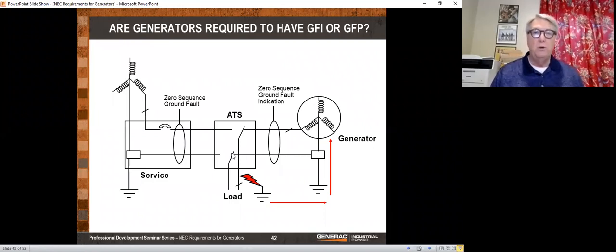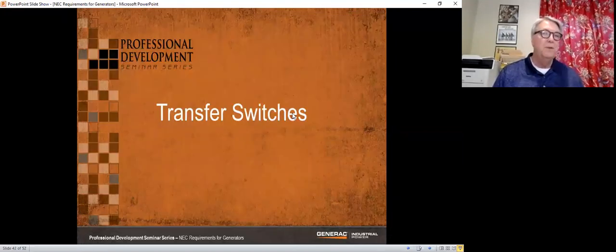If you used a 3-pole switch there, then this would just be a neutral bus bar. You wouldn't be switching that neutral. So now it would come out, it would go through here, then it would come down into your fault. But because with a 3-pole switch there would be no neutral to ground bond at the generator, it would have to come back through the service. And when it came back through the service, it would go through this zero sequence ground fault. It would trip your utility breaker. Then it would come back to the generator. The utility breaker would trip. The generator would not be able to see the ground fault because it came out through that zero sequence and came back through the zero sequence. It doesn't see the imbalance. So that's why you need your 4-pole.